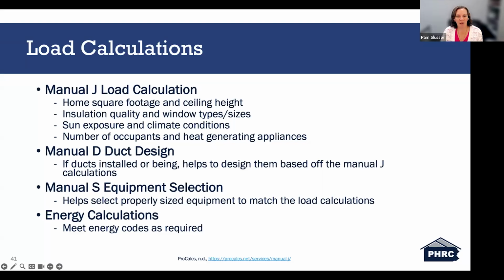So once the load is calculated, the Manual D is used to design the duct work. If ducts already exist, we verify whether they're sized and laid out appropriately. If ducts are being installed for the first time, the Manual D helps determine the duct diameter, the airflow distribution, and static pressure calculations based on the Manual J output. So properly designed ducts are essential for balanced airflow and occupant comfort.